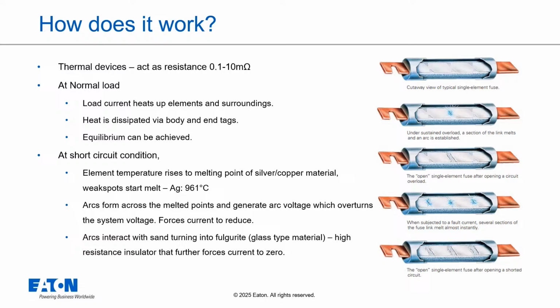Now, if a short circuit condition occurs, the current spikes dramatically. This rapid increase in current causes the fuse element's temperature to rise very quickly, reaching the melting point of the silver or copper material. The weak points, those neck down areas, melt first. Silver, for instance, melts around 961 degrees C. When the link melts, arcs form across the gaps. These arcs generate an arc voltage. This arc voltage actually works against the system voltage, helping to force the current to reduce. The arcs then interact with the silica sand filler, and this interaction turns the sand into a glass-like material called fulgurite. Fulgurite is a high resistance insulator, and it further helps to quench the arc and force the current down to zero, clearing the fault.